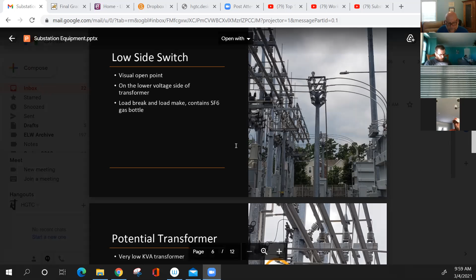Yes, sir. We talked about PTs and CTs a little bit. These are potential transformers. They're very low kVA, maybe. I think Professor Shoemaker said they were maybe 1.5 kVA, and they are just used for measurements of high voltage in substations. I never thought about that a whole lot until I started going into substations and saw how they monitored voltage, the breakers and all. I didn't ever see any high numbers like at Duke Energy. Our primary voltage was 13,200 phase to ground, 23 kV phase to phase, pretty high. And I always look for that number, but there's no way they run 13,200 volts down inside of that cabinet to monitor that voltage. So they would use those potential transformers to step that down to a readable level.